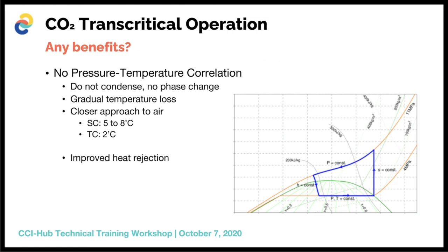A lot of people ask whether there are benefits to operating a plant in transcritical mode. There actually are. The first benefit is that there is no pressure-temperature correlation — you do not condense your refrigerant on the high side, so there is no phase change. Instead, there is a continuous drop in temperature as it goes down according to ambient conditions, giving you the ability to have a closer approach when working in transcritical mode.